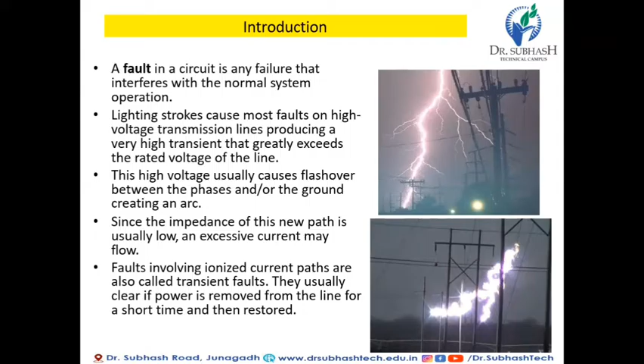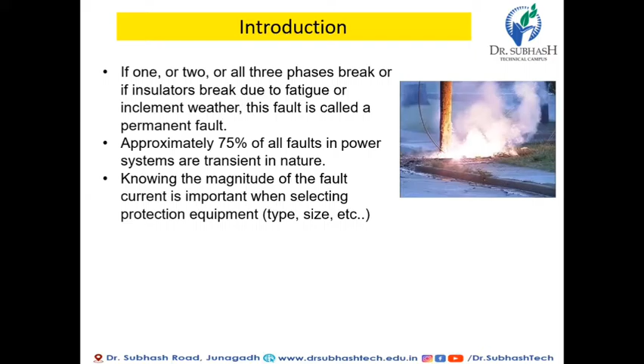Short circuit is the most common and dangerous fault occurring in the power system. When a short circuit occurs, a heavy current called short circuit current flows through the power system and its equipment. In order to protect the equipment during faults, fast acting circuit breakers are put in the lines. For these circuit breakers, the fault current has to be calculated. Short circuit calculations are very important since they provide data which is required for designing the protective scheme for the power system.